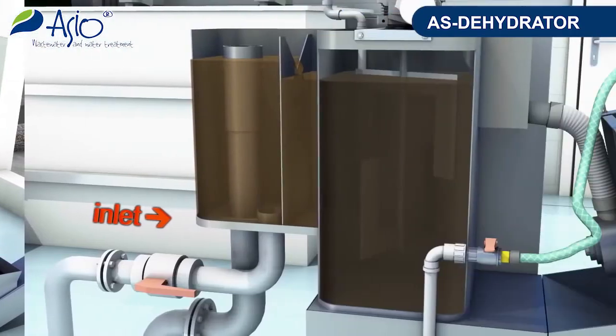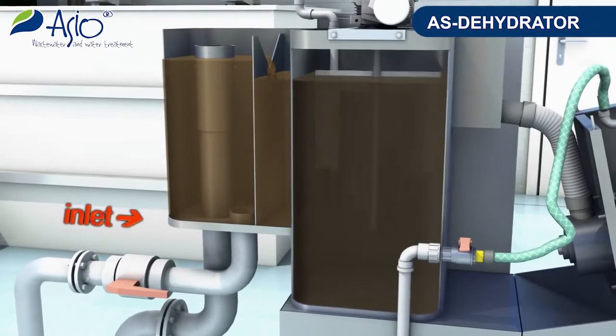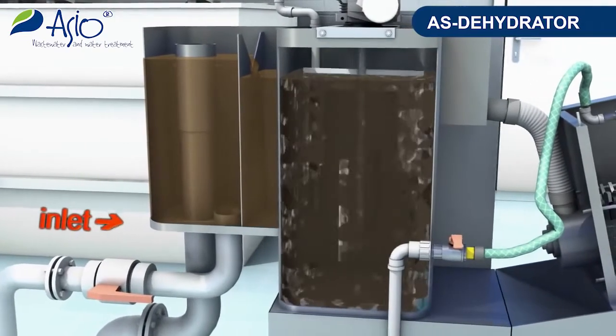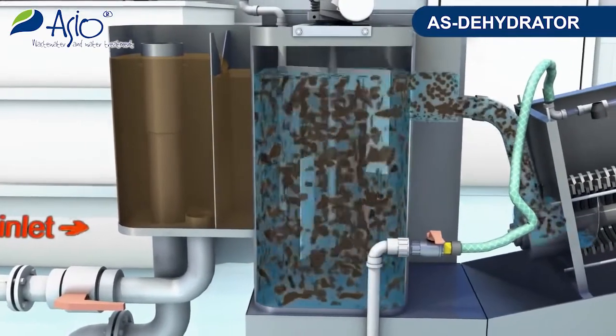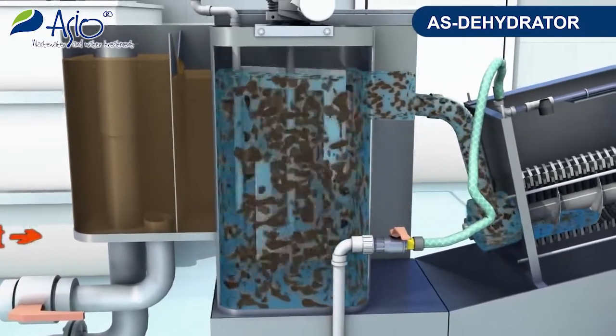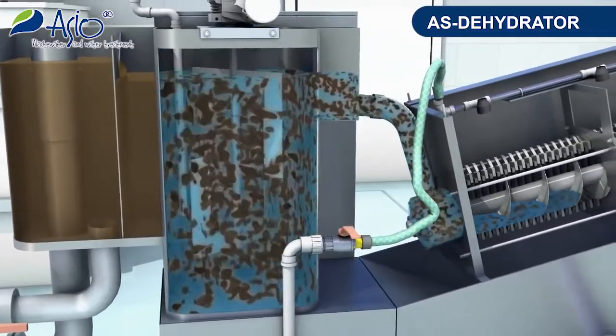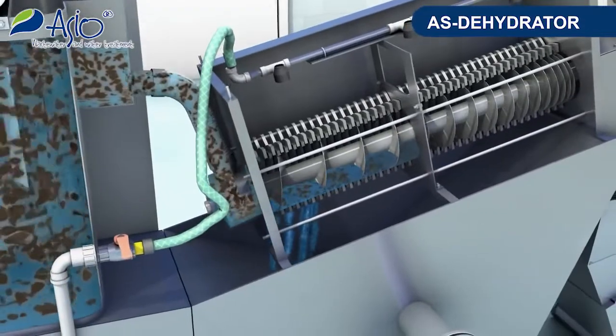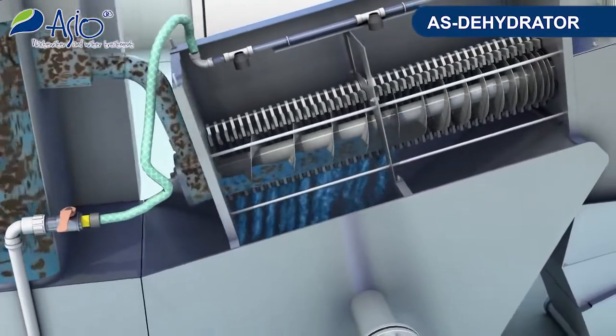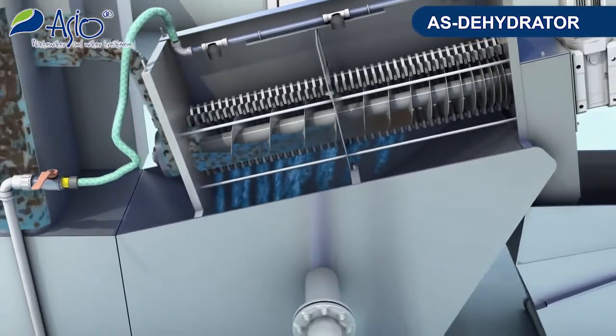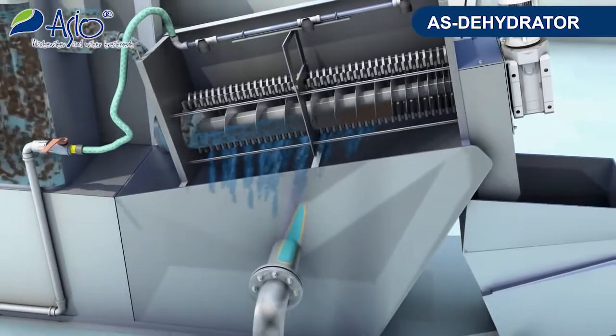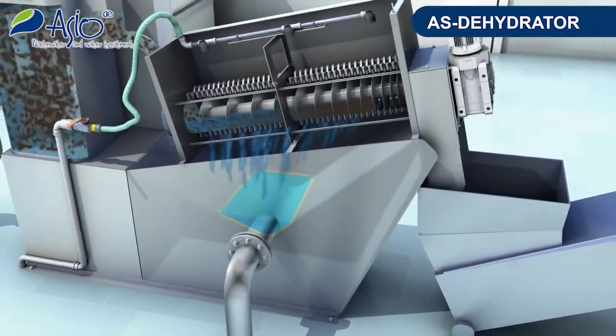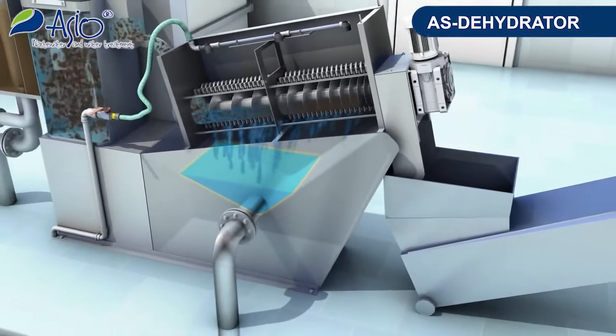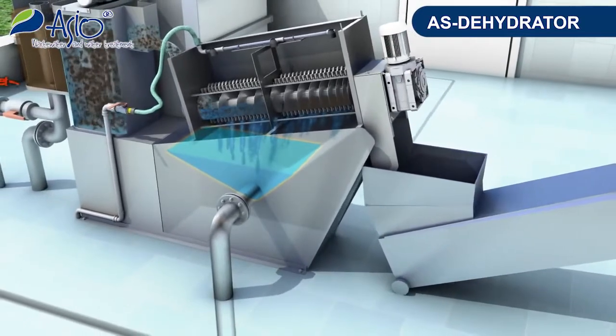The reaction of the flocculant with the sludge causes clearly defined flakes to be formed in the dehydrator flocculation tank and subsequently brought into the dewatering drum. The drum consists of a spiral conveyor enclosed in a tube, in which there are alternate fixed and moving baffles. The spiral rotation moves the sludge to a thrust plate. At the same time, the water stream squeezed out of the sludge flows away between the baffles.